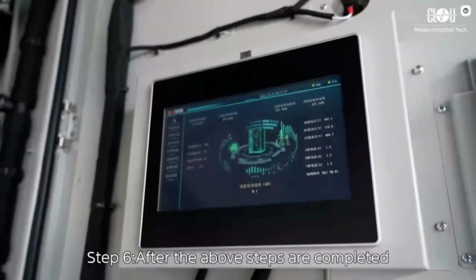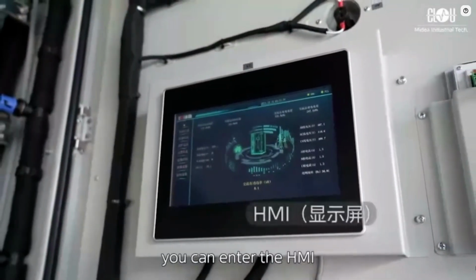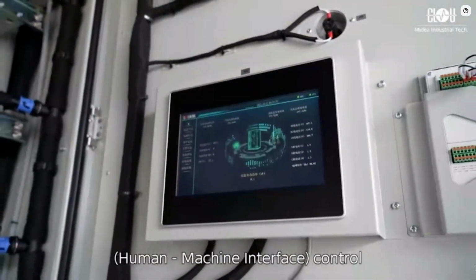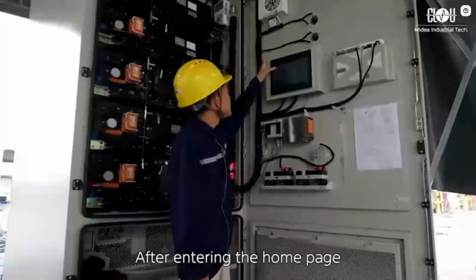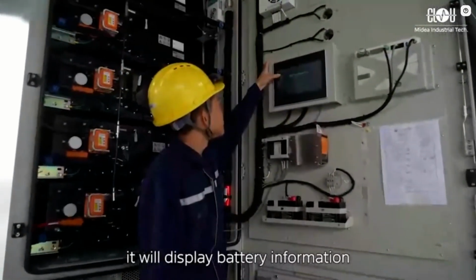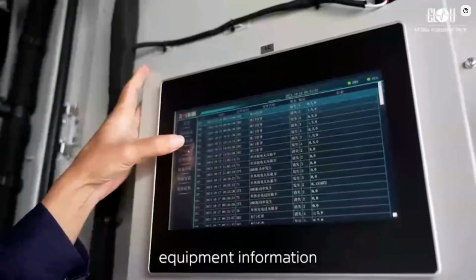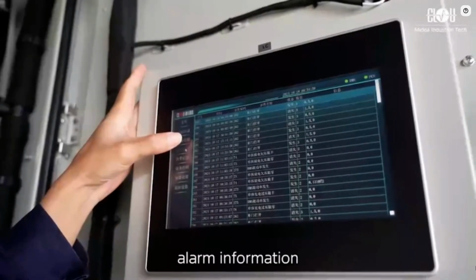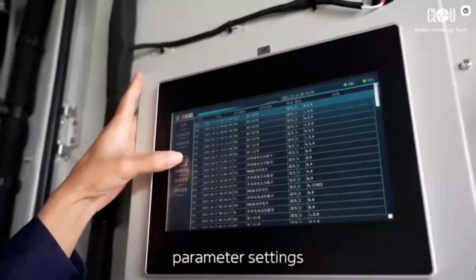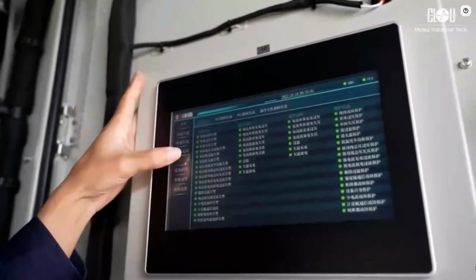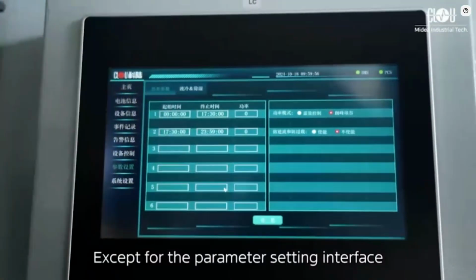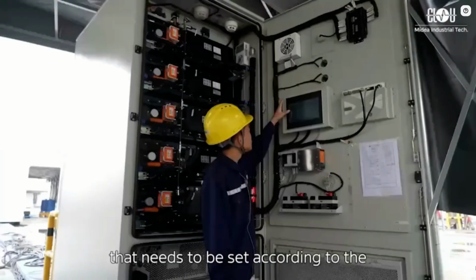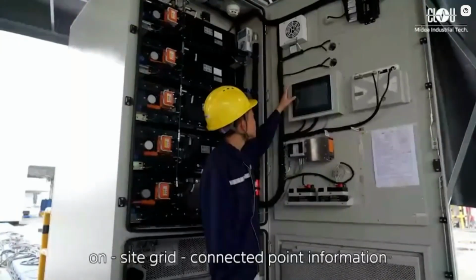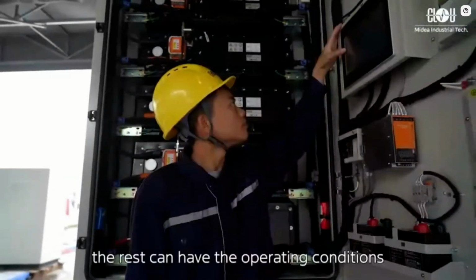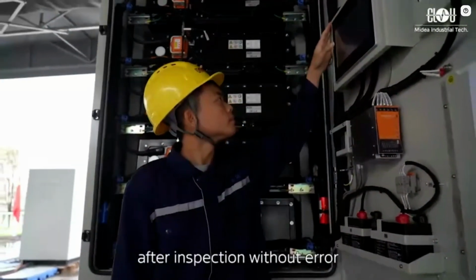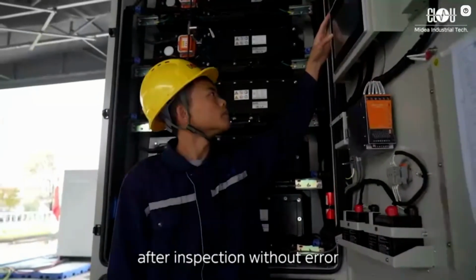Step 6. After the above steps are completed, you can enter the HMI, Human Machine Interface control. After entering the home page, it will display battery information, equipment information, event records, alarm information, equipment control, parameter settings, and system settings. Except for the parameter setting interface, which needs to be set according to the on-site grid-connected point information, the rest can be operated after inspection without error.